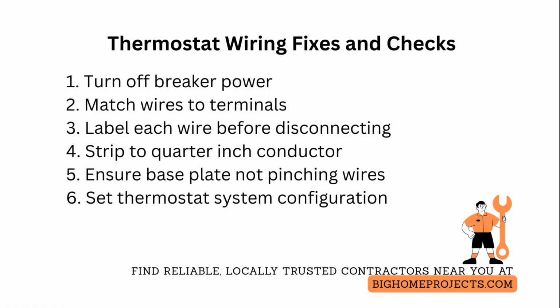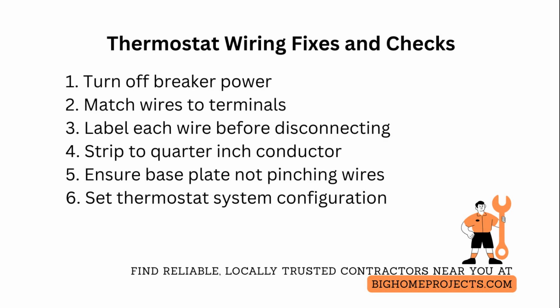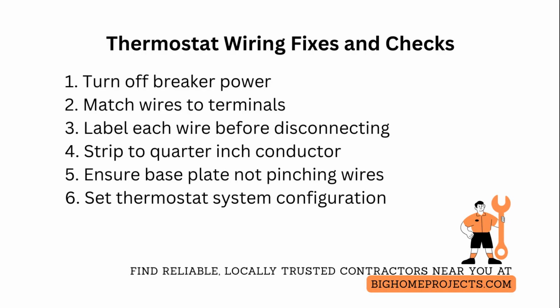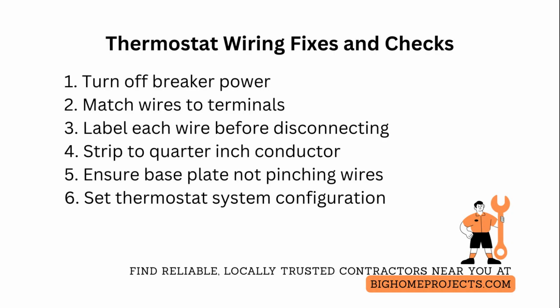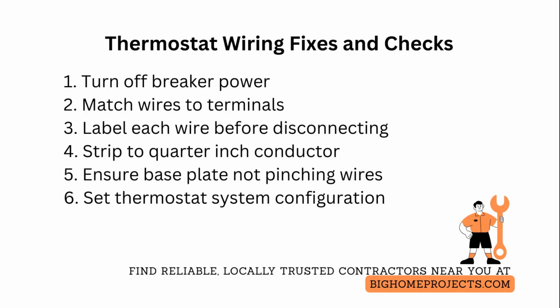terminals. Verify the new thermostat's base plate is not pinching wires or contacting the wall box metal. Add a small non-conductive spacer if needed, and ensure the wall box is properly grounded but not contacting low voltage wires. Confirm the thermostat model supports your system type, heat pump, conventional split system, or single-stage furnace, and set the internal configuration or installer settings accordingly. Misconfigured dip switches or software settings can energize both heat and cool coils simultaneously.